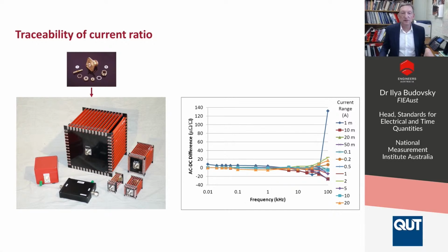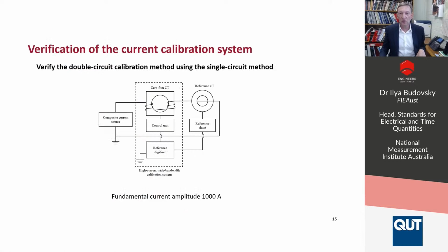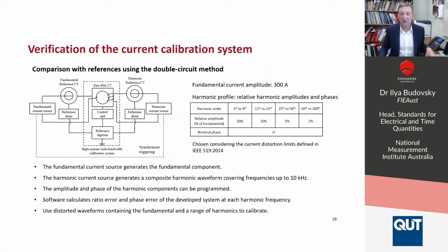So we've used these shunts to first calibrate the 200 ampere reference CT, and then we do a simple comparison with the 4000 amp CT, putting 5 turns on the 4000 amp CT to make the current equivalent to 1000 amps. Now, the idea here is to calibrate the reference CT this simple way, and then using the double circuit to prove that the double circuit actually works, and then to calibrate it using separate references.